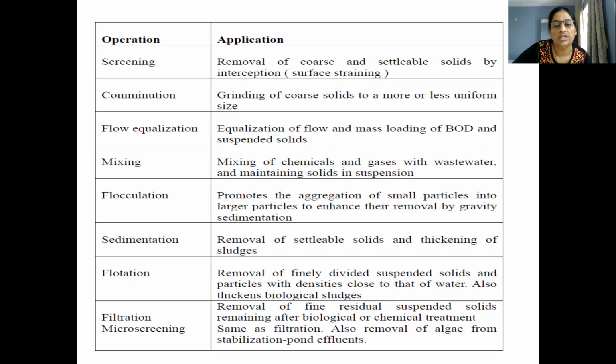Then flotation: removal of finely divided suspended solids and particles with densities close to that of water, and it also thickens biological sludges. Usually this process is for the removal of finely suspended solid particles with densities close to that of water, and because of that they remain in suspension at the surface, acting as floating material.